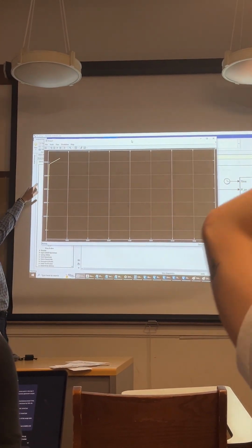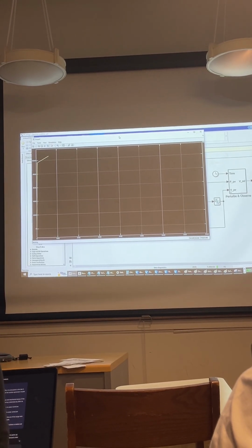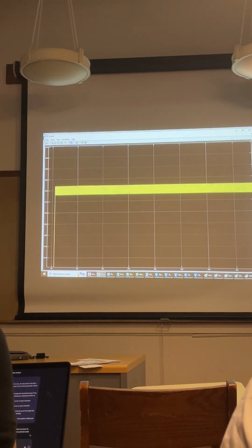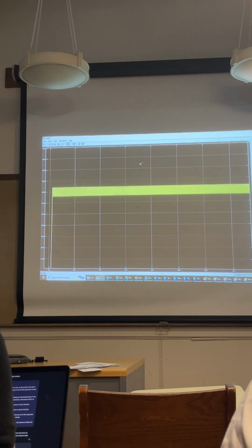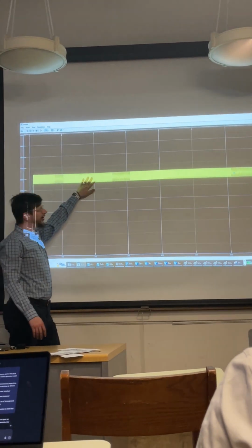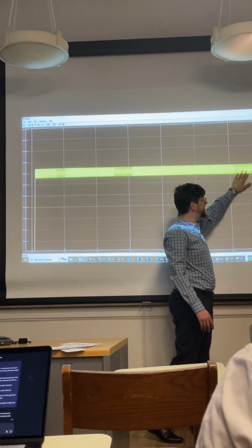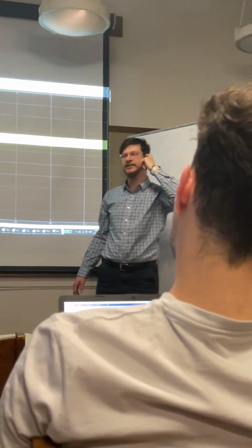We can change that. You see that? It's still running, okay? So you see that the power keeps increasing until it's going to find the ideal power around that voltage. Okay? So this is what we're seeing here. The operation of the perturb and observe. The main point that I want to make, as I told you earlier, is this. That the perturb and observe keeps increasing and decreasing the voltage at several steps per second to see if the power is going to increase or decrease.